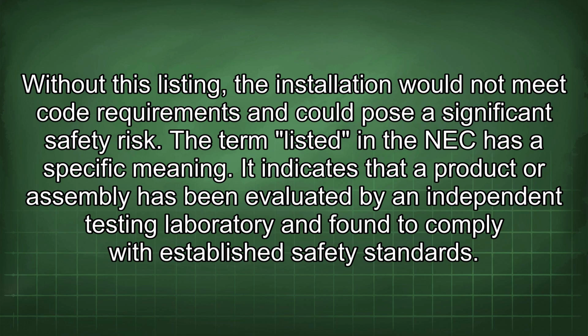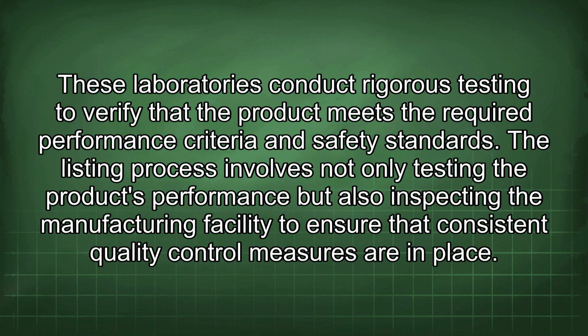The term listed in the NEC has a specific meaning. It indicates that a product or assembly has been evaluated by an independent testing laboratory and found to comply with established safety standards. These laboratories conduct rigorous testing to verify that the product meets the required performance criteria and safety standards. The listing process involves not only testing the product's performance but also inspecting the manufacturing facility to ensure that consistent quality control measures are in place.